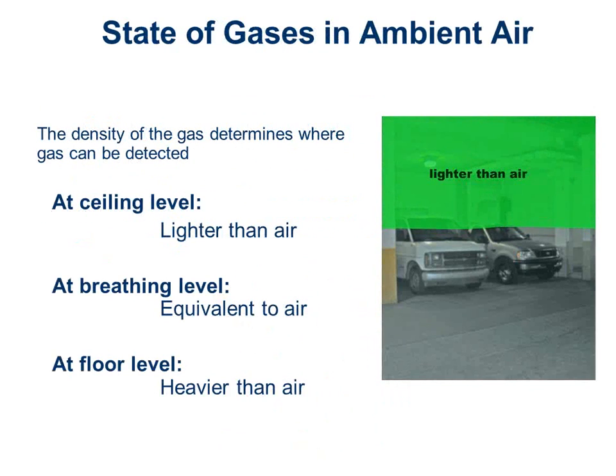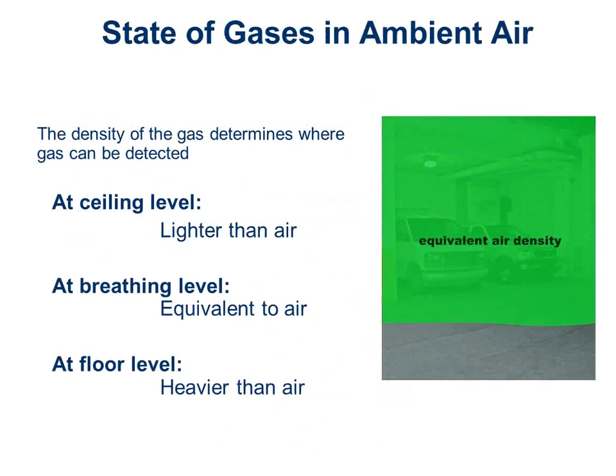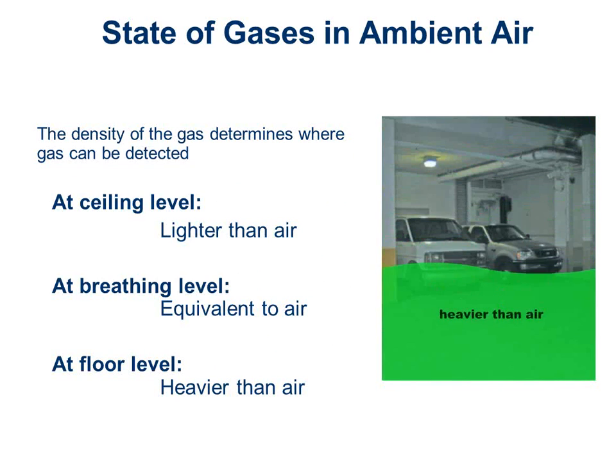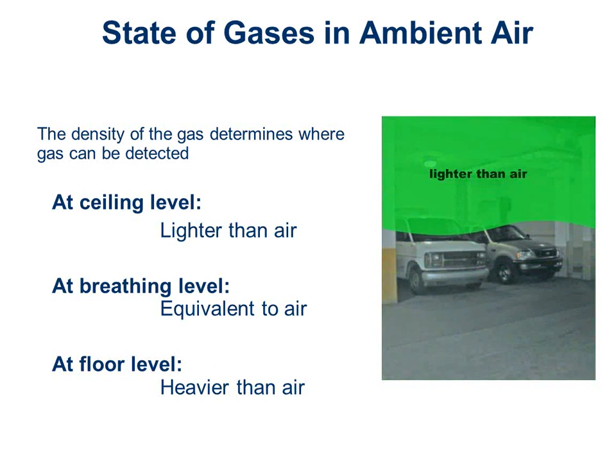Regardless of what type of gas sensor we're working with, whether it's one I just mentioned or others I'll mention later, like hydrogen or refrigerants, I have to decide: is this gas lighter or heavier than air? Why do I need to know that? Because I need to know whether I want the sensor at the floor, up toward the ceiling, or in the breathing zone - 4 to 6 feet off the ground.